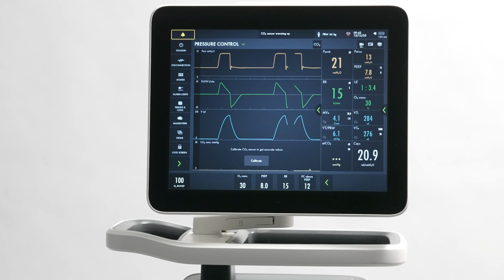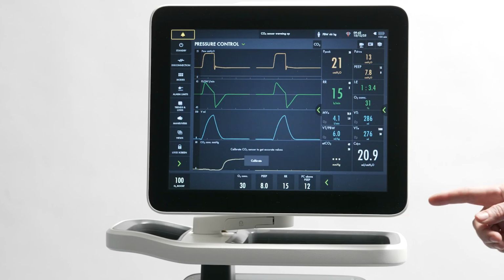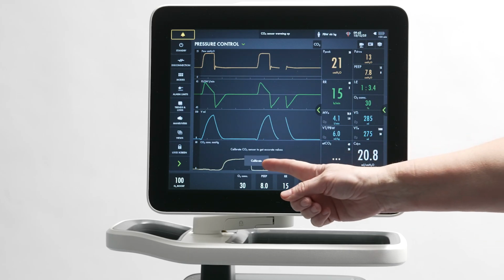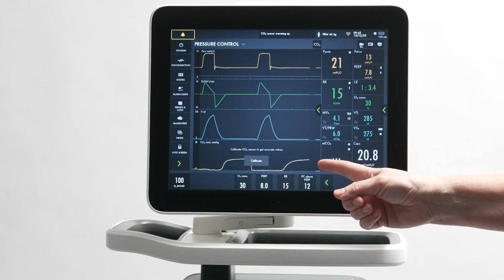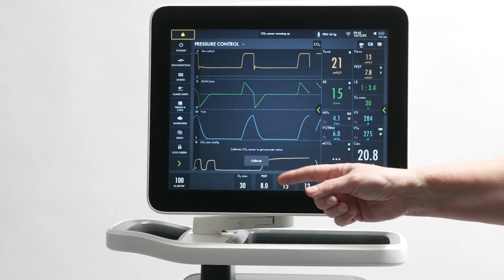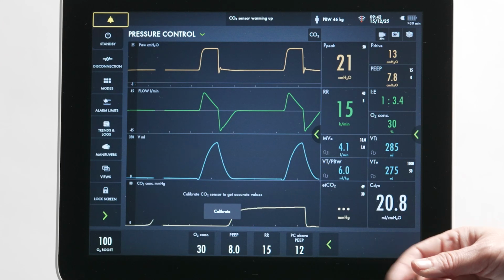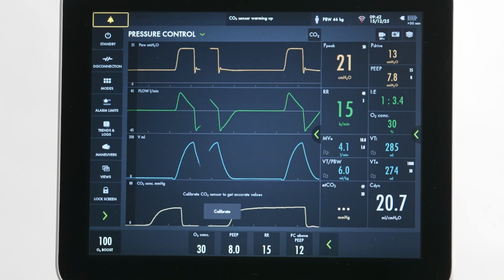If calibration of the CO₂ sensor is not performed and the CO₂ sensor is connected to a patient circuit, the CO₂ waveform is displayed, but no measured values will be displayed. Until calibration is complete, the waveform will have reduced accuracy and no CO₂ value will be displayed.